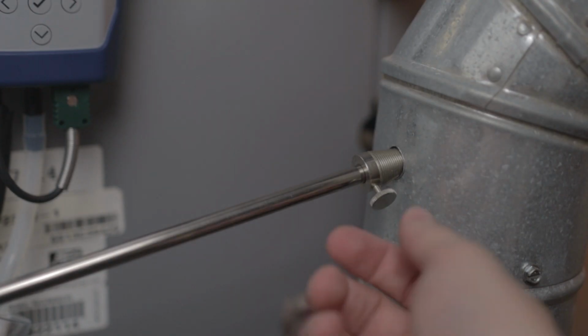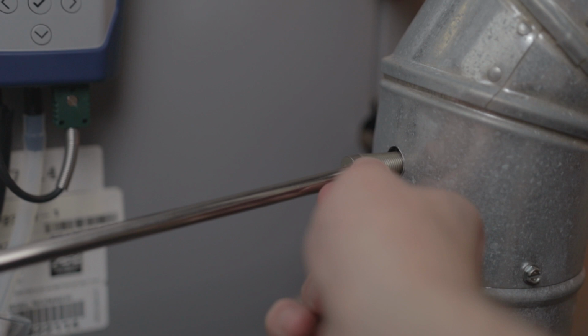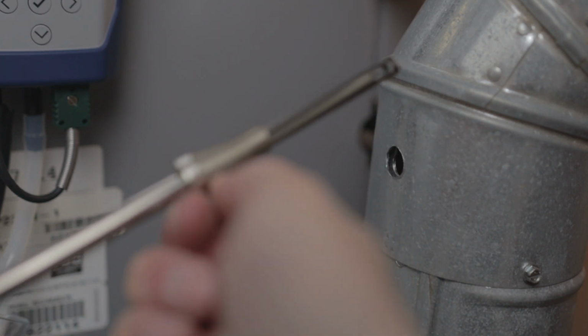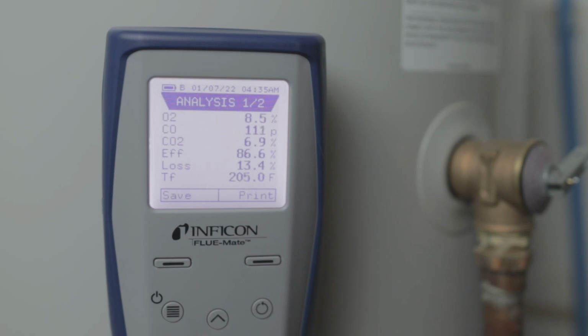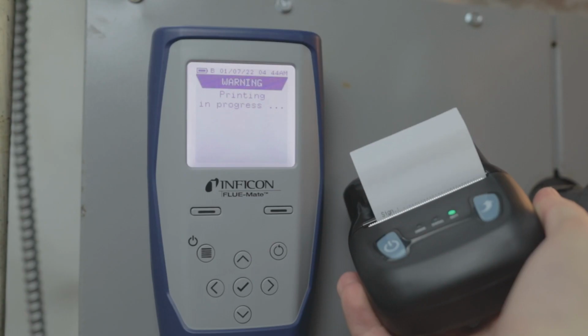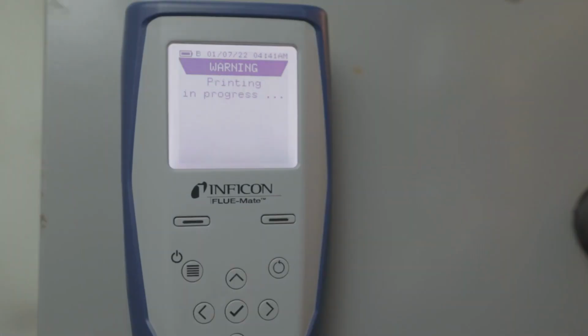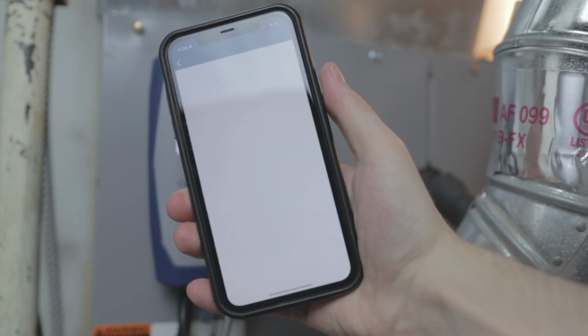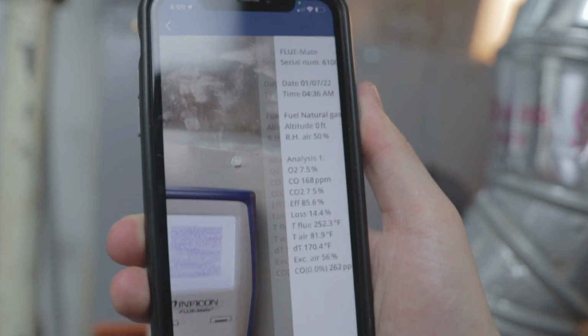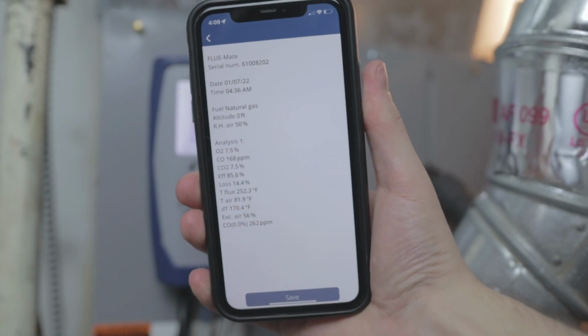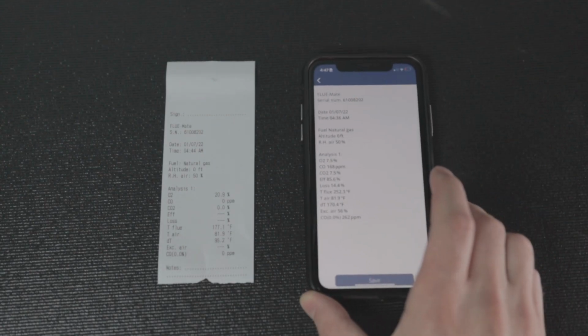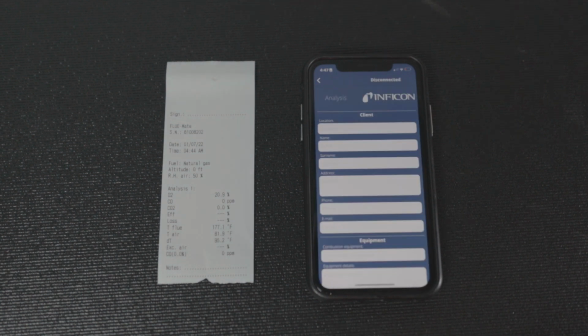When finished, remove the sample probe and any other connections. Use caution as the sample probe and flue stack can be very hot. You have the option to save or print the analysis report. If Save is selected, FLUE will save the test results locally on the device. Print allows you to print the test results with a Bluetooth printer or generate a unique QR code you can scan to quickly transfer the analysis report to the FLUE mobile app. Both of these options allow you to keep a record and share documentation.